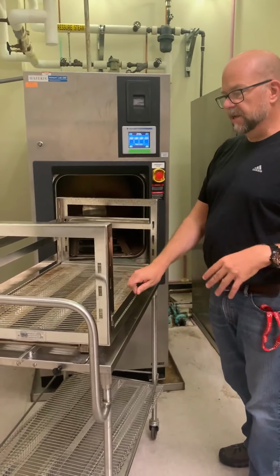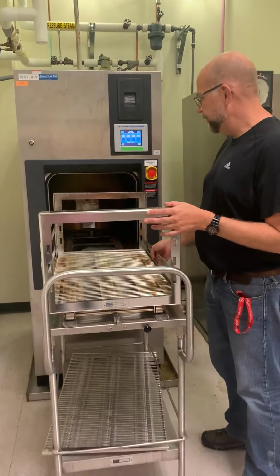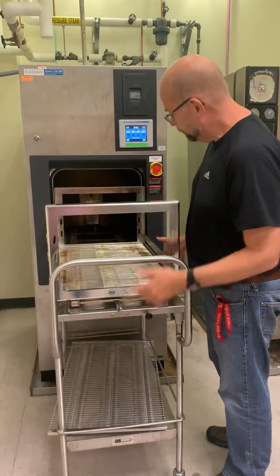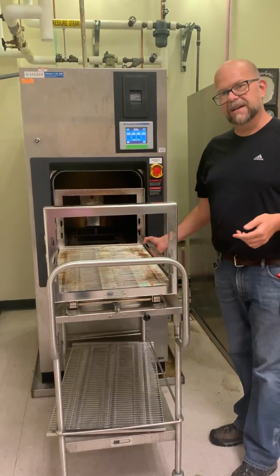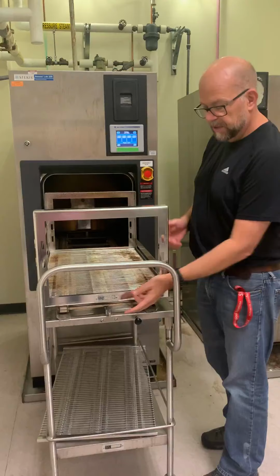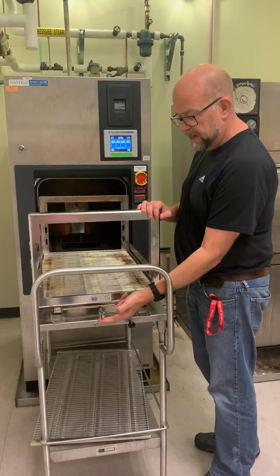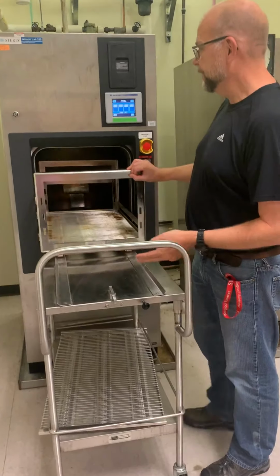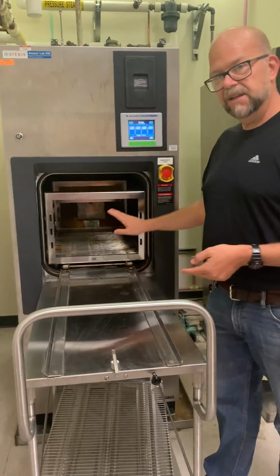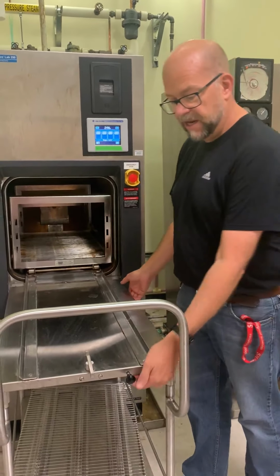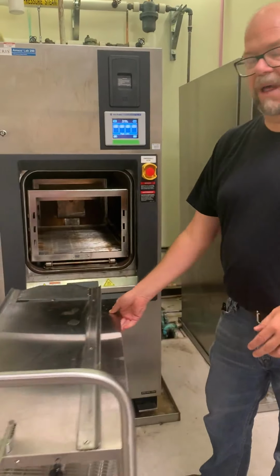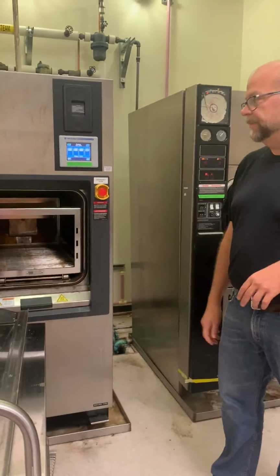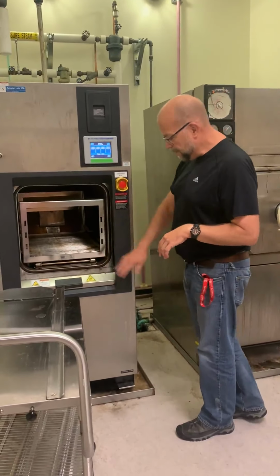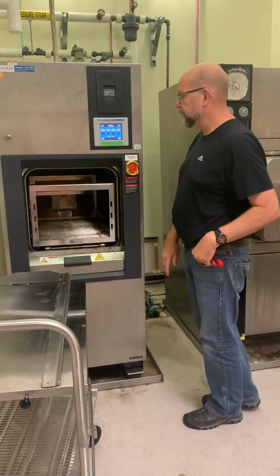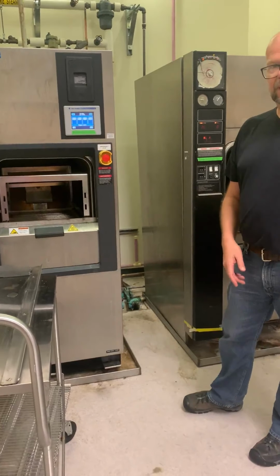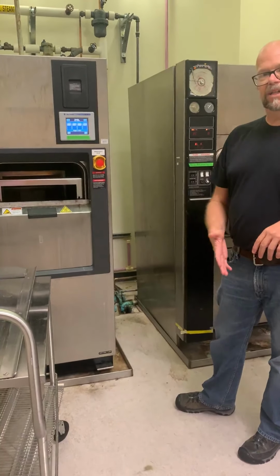So you load your material up onto the cart, push the cart up and it locks in place. You release the cage by lifting up on this trigger, sliding your cage all the way into the chamber, and then pushing on the black knob and pulling the chamber back again. So once we've got our material loaded into the chamber, we press the foot pedal at the bottom and it automatically closes the door.